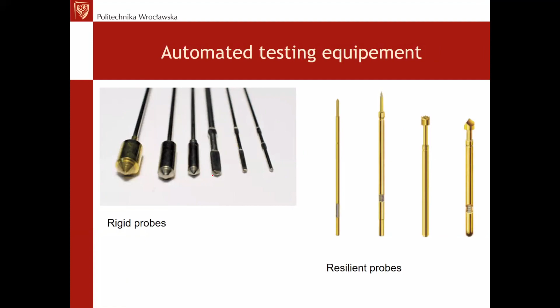Then on the ATE for testing, there has to first be prepared a template with the probes placed where the PCB has its testing points. In this in-circuit testing, when there is contact, a stimulus is delivered from those large cabinets where there are various signal generators and pattern generators, all programmable and controlled by some application. The operator just presses start, and then the ICT test runs, and the board is tested automatically. So this is in-circuit testing.